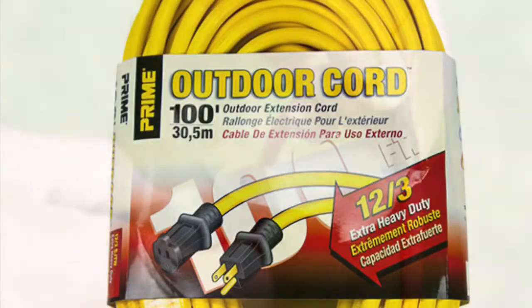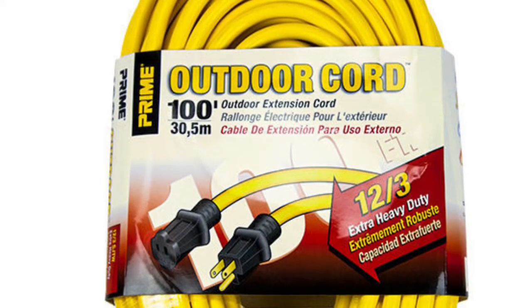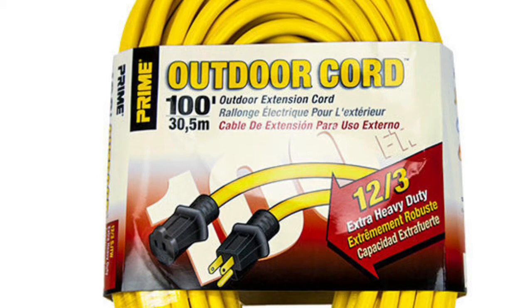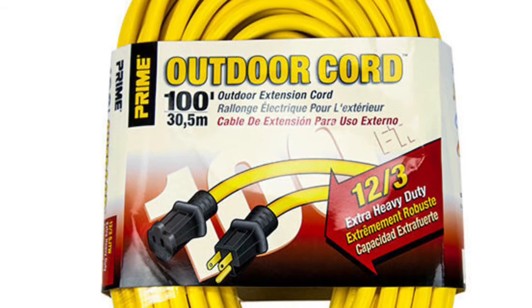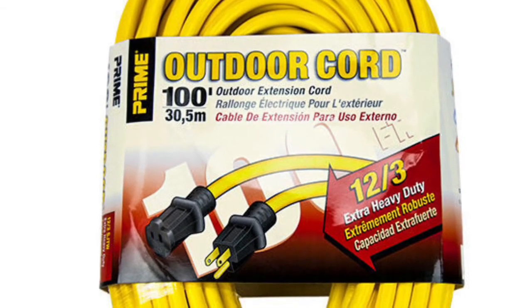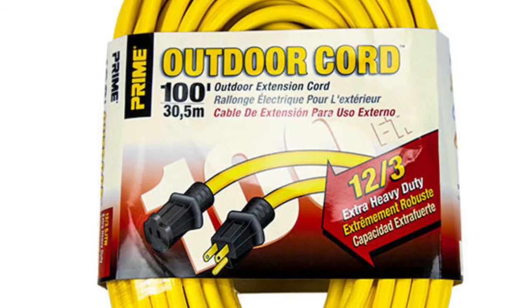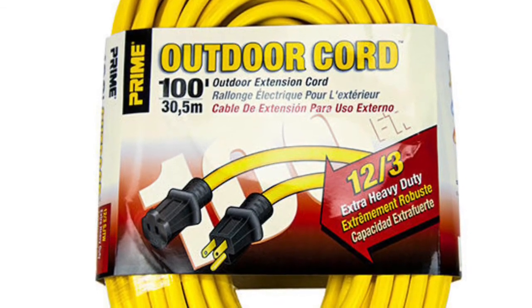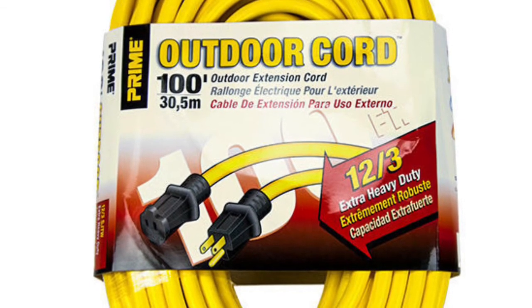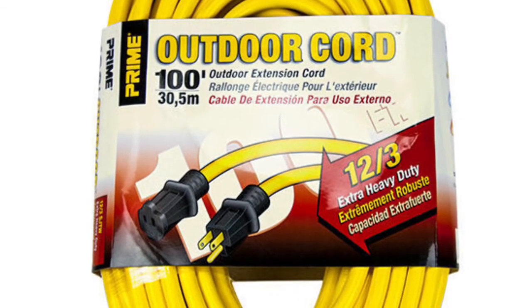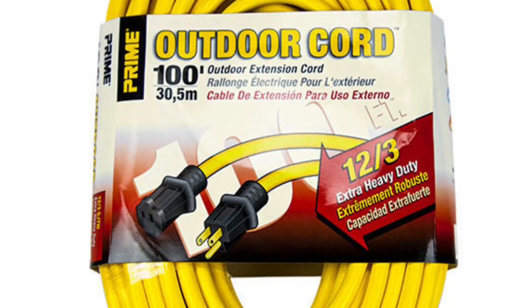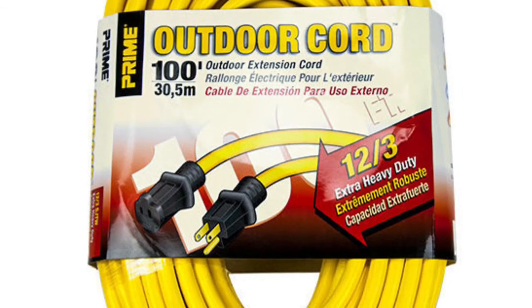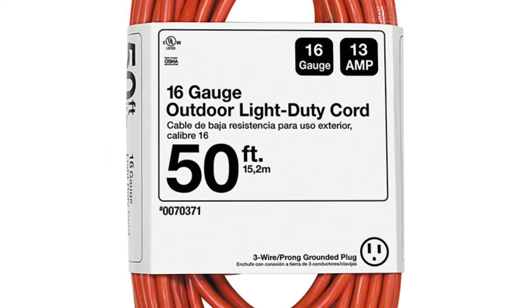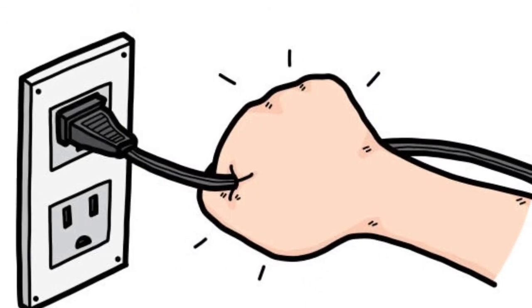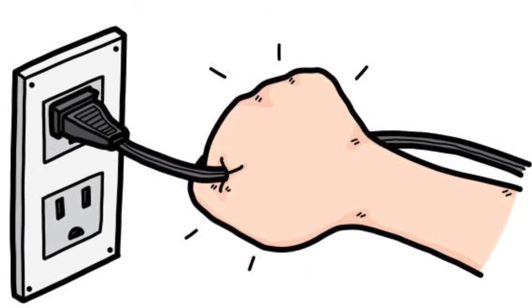Extension cords are rated for use, and only hard or extra hard usage extension cords can be used on construction job sites. Examples of hard usage types include ST, SO, STO, SJ, SJO, SJT, and SJTO. Extension cords must be durably marked with one of the hard or extra hard usage designation letters, size, and number of conductors. Do not use light-duty cord on construction job sites. Remove cords from receptacles by pulling on the plug, not the cord.